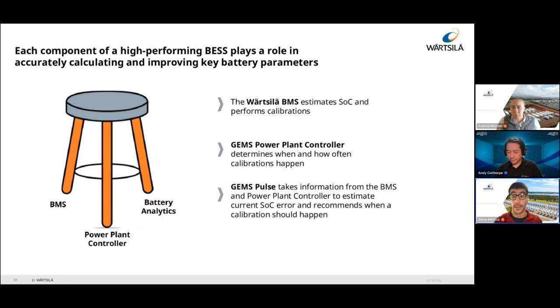And then a battery analytics solution also looks across the site level, and it is looking to optimize the performance of these calibrations. You might have a problem child who needs to calibrate really frequently because the imbalance is high or the SoC accuracy is low, or you might have a star pupil that can actually wait a long time between calibrations, maybe every 4 or 6 months or something.